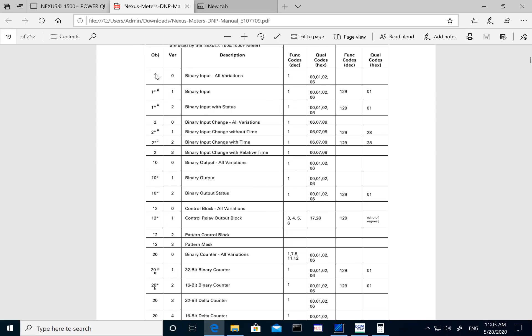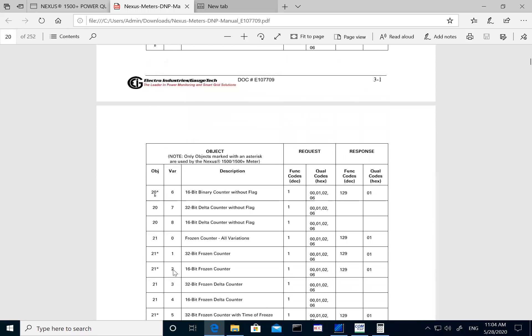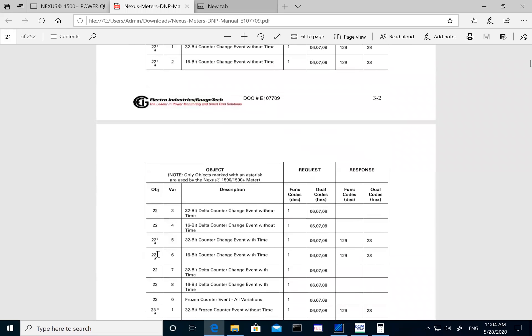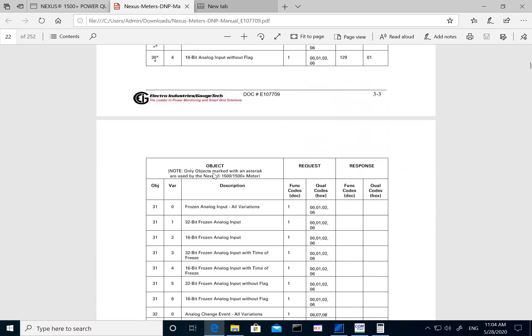There is a list of objects that the meter supports. For example, object 1 is binary inputs, object 10 is output, object 20 is counters, and object 30 is our analog signals. Object 30 analog input is what I've seen most customers use — that object can be used to pull real-time readings of voltage, current, power, frequency, and power factor from the meter.